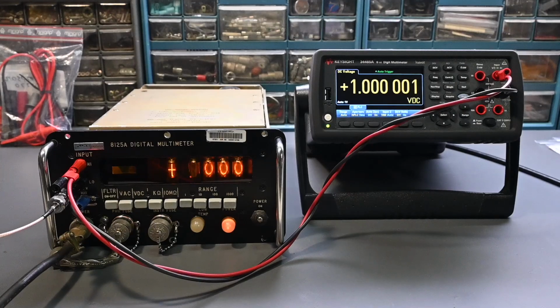And everything is measured against the Keysight 34465A digital multimeter that you see sitting here. So that digital multimeter is under a factory calibration, so it's very, very accurate. And so basically everything is just measured against that multimeter. So for example, some of the resistors that I have are not necessarily precision resistors. Like I think the 1 megohm resistor that I used is a 5% tolerance. So it's not spot on 1 meg, but whatever its value is that it measured on the Keysight, that's what the 8125A was then calibrated to end up showing. So basically the 8125A has been calibrated against the Keysight and is measuring exactly the same readouts as what the Keysight shows.